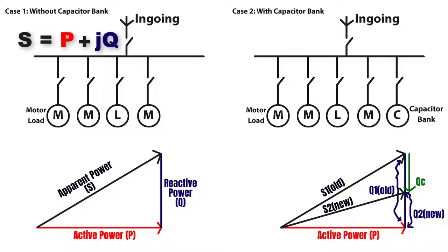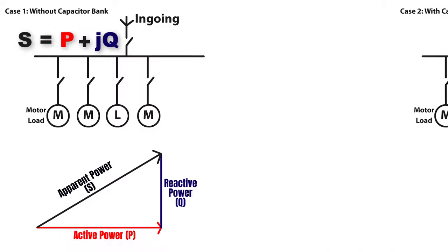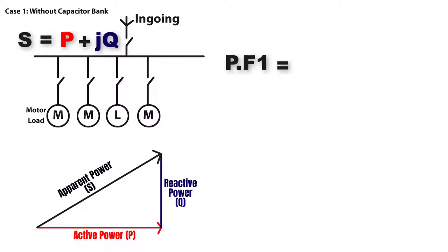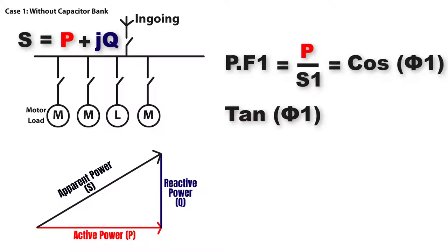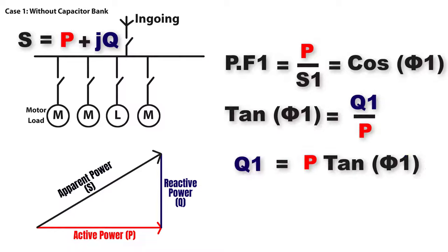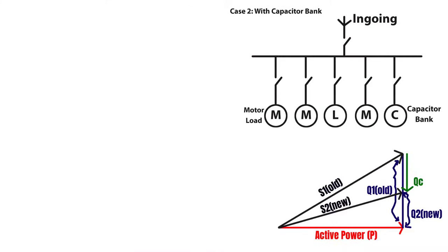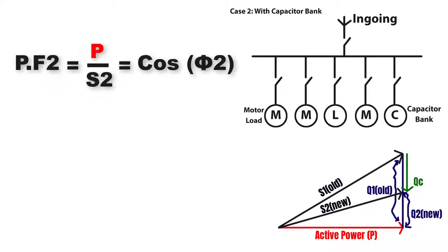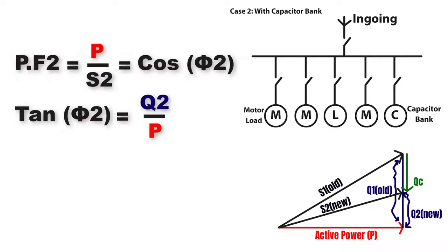Let's assume we have a system with no power factor correction and then connect it to a power factor correction system. Case 1 — before connecting the correction system: power factor 1 equals P over S1, which equals cosine phi 1, and tan phi 1 equals Q1 over P, so Q1 equals P times tan phi 1. Case 2 — after connecting the correction system: power factor 2 equals P over S2, which equals cosine phi 2, and tan phi 2 equals Q2 over P, so Q2 equals P times tan phi 2.